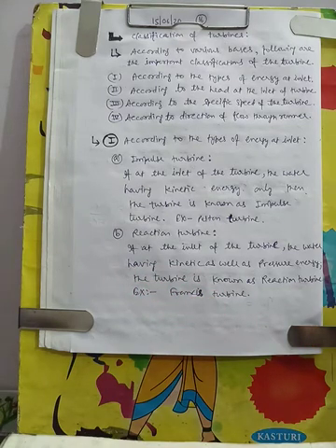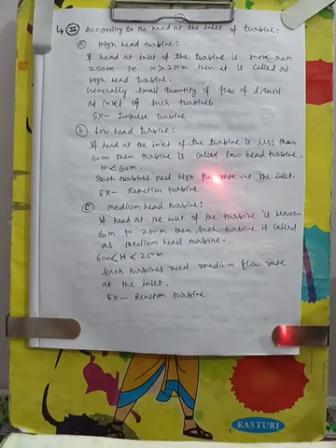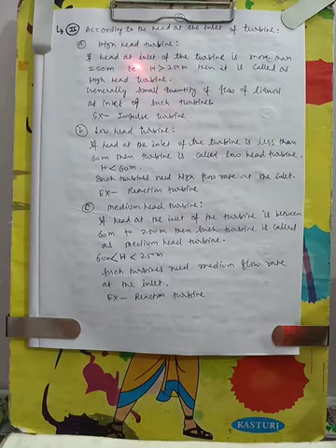Now we see according to head at the inlet of turbine. If head of water or jet at the inlet of turbine is greater than 250 meter, then such a turbine is called high head turbine.